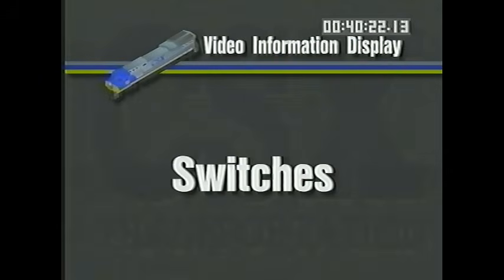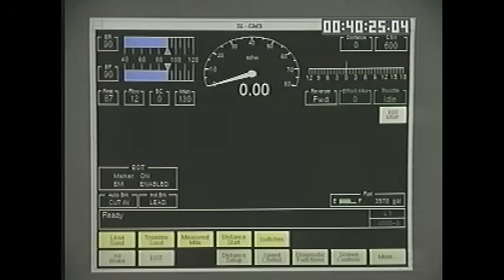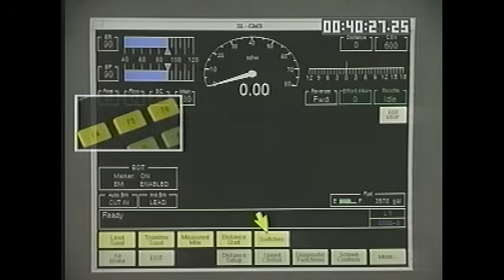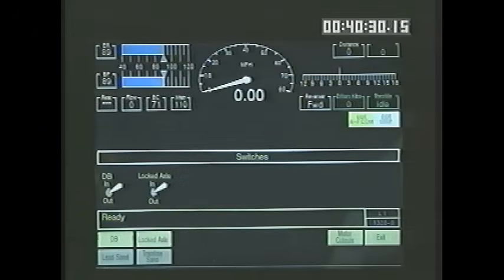Let's take a look at where another important menu selection takes you. From the main operating display, F5, Switches, accesses the Switches screen. The menu choices change, and the F1 and F2 keys control the on-screen switches. The dynamic brake cutout switch cuts out dynamic braking on this locomotive. When in lead, train line signals will continue to be sent to other units in the consist. The locked axle cutout switch cuts out the locked axle alarm. Wheel slip protection is still active.